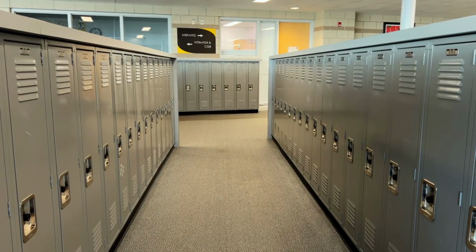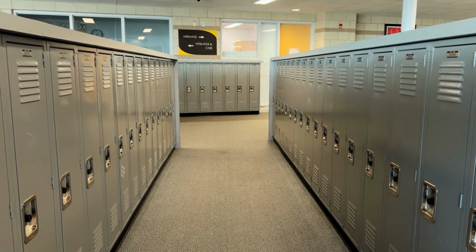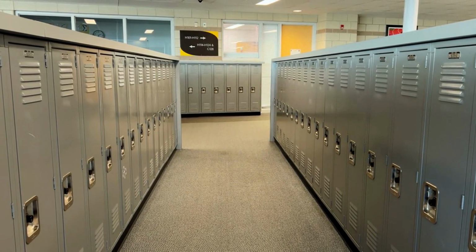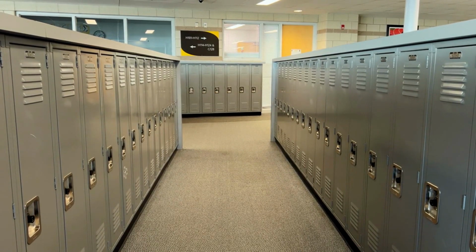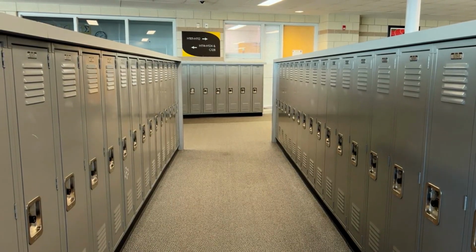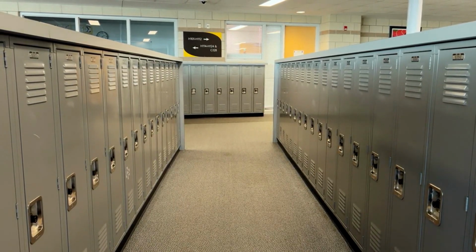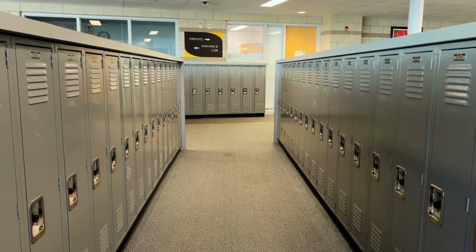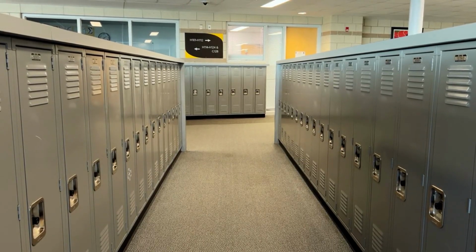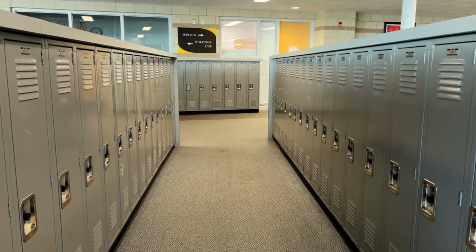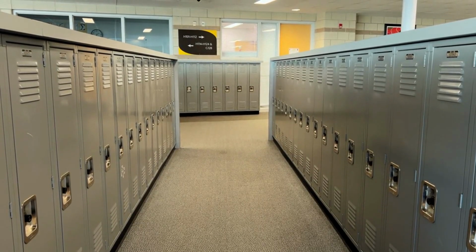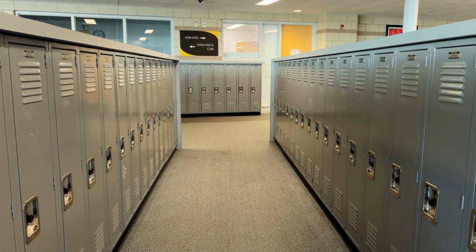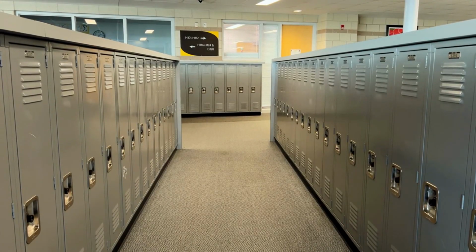6.2.8. Wardrobe/locker ventilation in SCA project. Design approach. 1. Mechanical exhaust ventilation is not required for wardrobe closets and/or locker areas in classrooms and corridors. 2. Wardrobe closets inside each primary school and intermediate school classroom shall be provided with bottom louvers to provide natural ventilation. 3. Corridor lockers shall be provided with top and bottom louvers for natural ventilation.